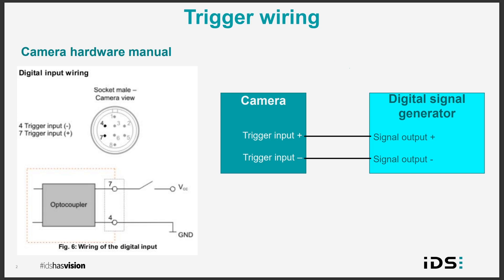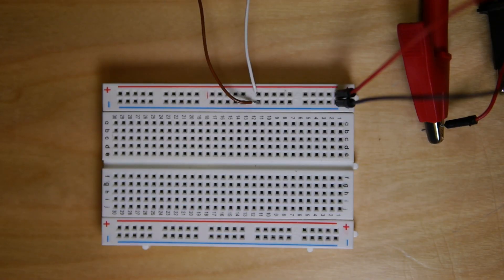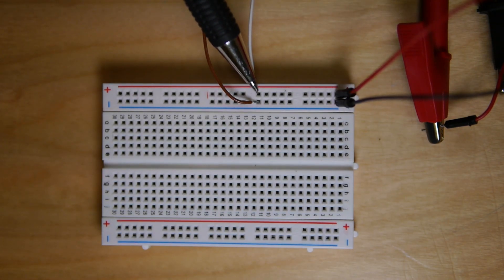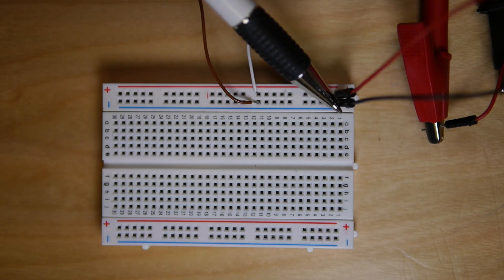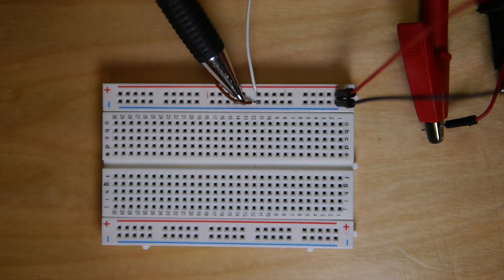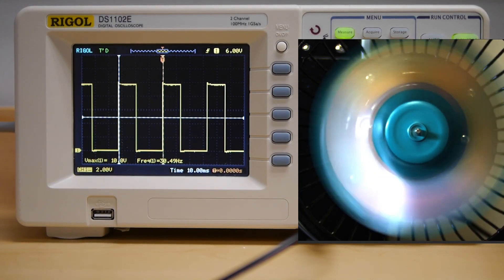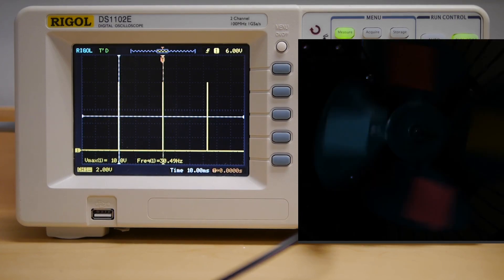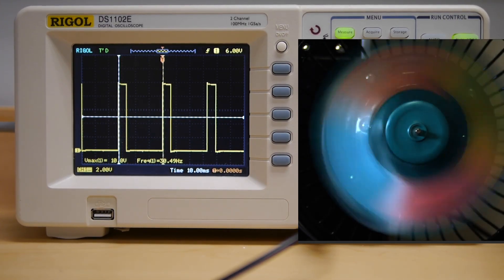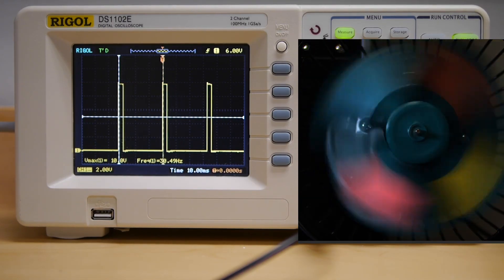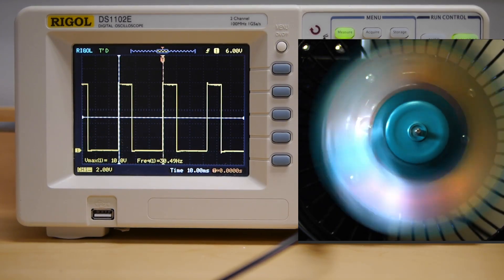Connect positive to positive and negative to negative. Following the digital input wiring guide, I connect the positive terminal of the digital signal generator to the positive trigger input white lead of the camera, and then connect the negative terminal of the digital signal generator to the negative trigger input brown lead of the camera. With the wiring completed, I can turn my attention back to Peak Cockpit, where the camera is capturing images. By modifying the frequency and duration of the digital signal, I can change the frame rate and exposure time of the camera. A basic trigger configuration such as this one allows the camera exposure to be precisely controlled by an external device.